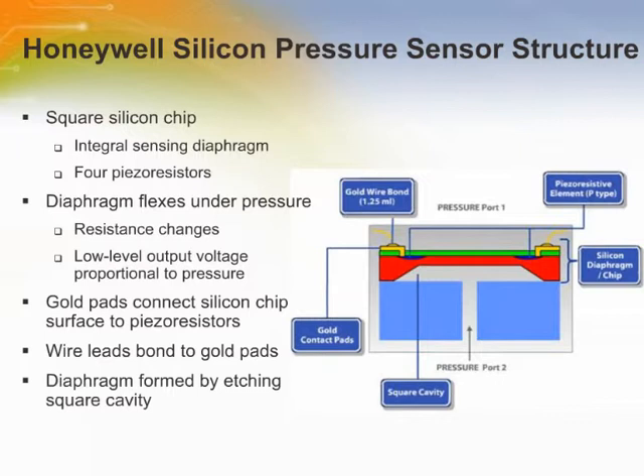Each Honeywell solid-state pressure sensor is developed around a square silicon chip with an integral sensing diaphragm and 4 piezo resistors. Pressure applied on the diaphragm causes it to flex, changing the resistance, which results in a low-level output voltage proportional to pressure. The sensing resistors are connected as a 4-active element bridge for best linearity and sensitivity.